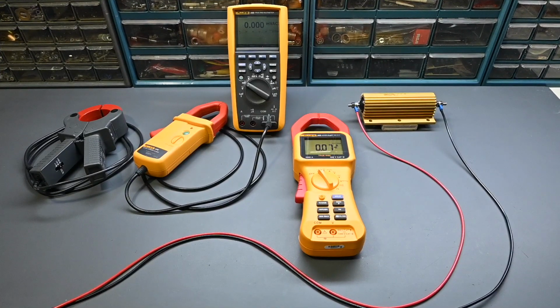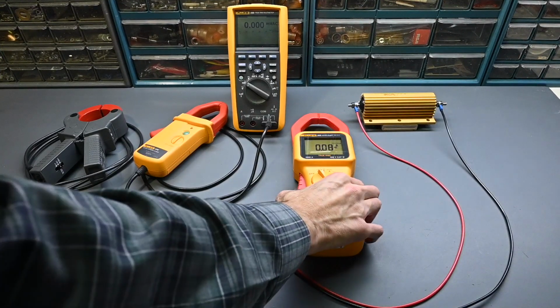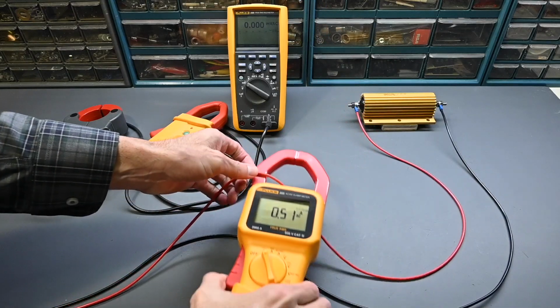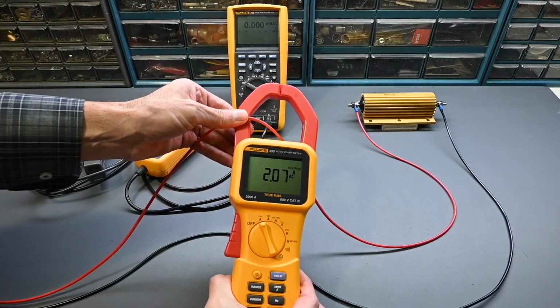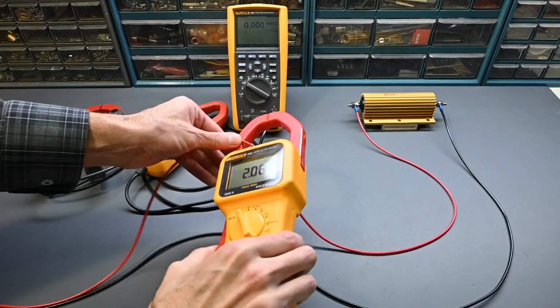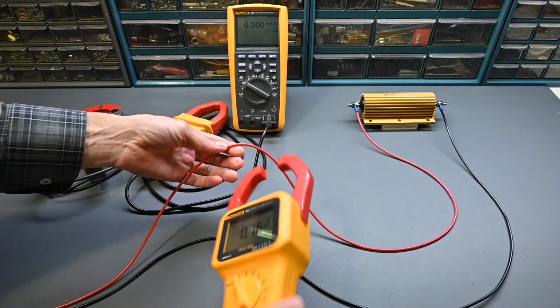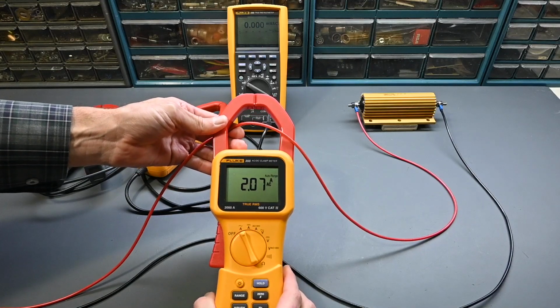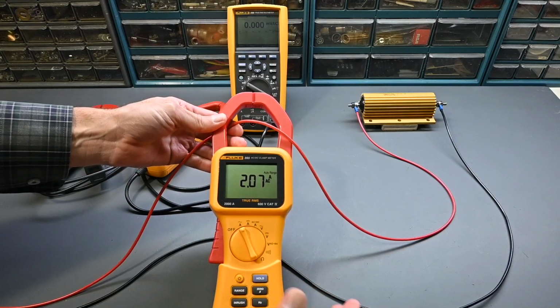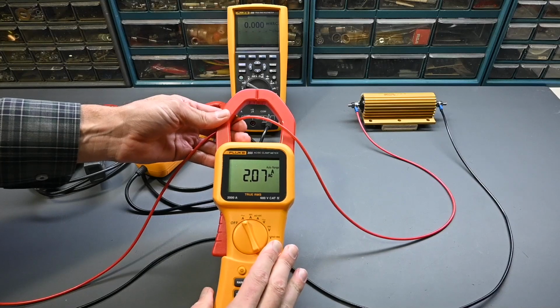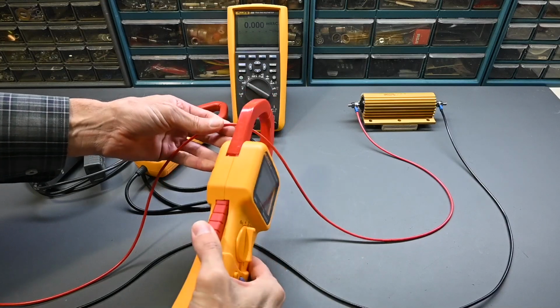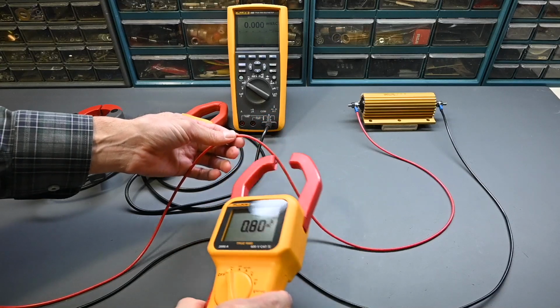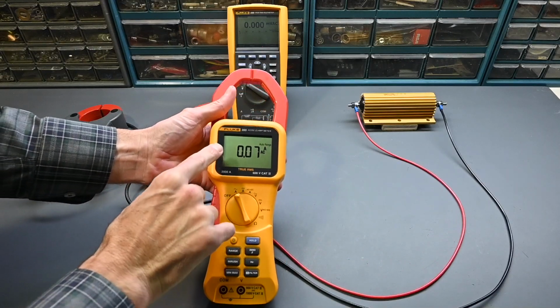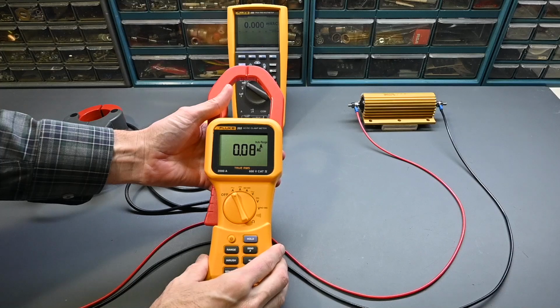So here are several things to remember when using a current clamp. If I take this clamp and go around the red test lead like so, you can see it's measuring 2 amps AC. It doesn't matter if the current clamp is facing this direction on the wire or if I go this direction on the wire, it's still the same displayed reading, and there's no displayed polarity because it's AC current. Now imagine if this is measuring DC current. If you have the clamp facing this direction on the wire or you go this direction on the wire, it will make a difference on the displayed polarity. So in one direction you'll have a negative symbol on the display.